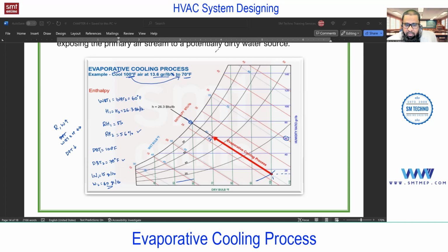Or else what will happen, the complete evaporation is going to happen in the room only. First of all, when water passes through a layer of wet mesh, or we can say honeycomb, it will extract the moisture. Apart from this, the water which is evaporated because of extracting the heat also stays in the room. So within no time the RH, the humidity, will increase. That's the reason that if you use an air cooler in the room without any exhaust, you will get a lower temperature, but you cannot breathe easily because of the higher humidity levels.